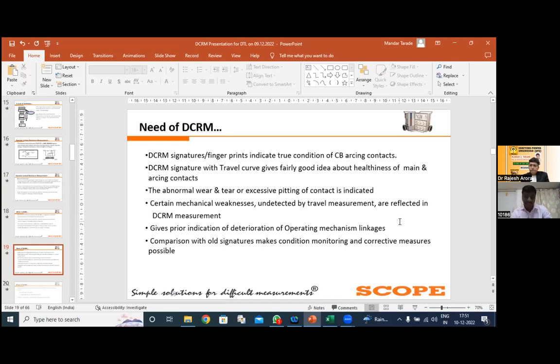That's why DCRM. One more important thing is that with the help of software, if you have data from the breaker installation or commissioning up to the present date, that means enough samples are available, you can simply compare the DCRM signatures with the old signature, and with the help of that you can comment on the healthiness of your contact. So this is about the DCRM test.